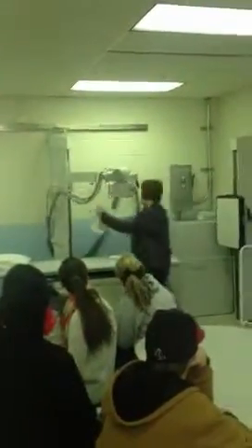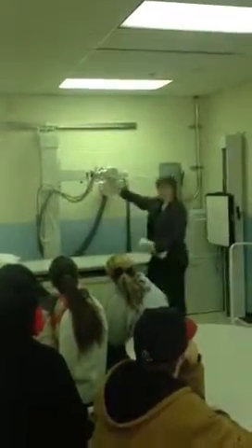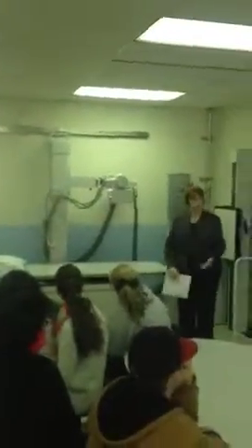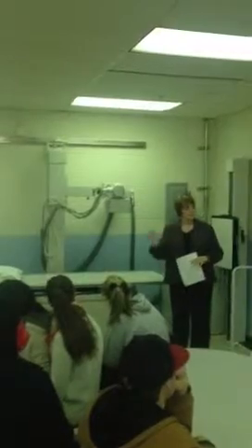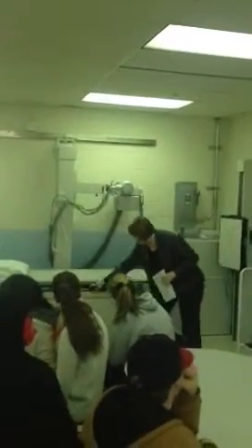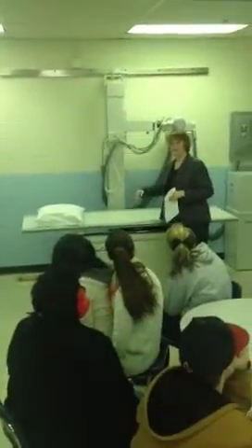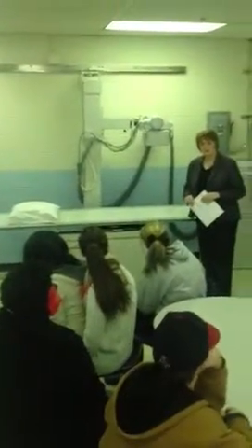Pretend this is a fluoroscopic unit. Use your imagination. X-ray tube's out of the way. You've got your big honker thing here. That imaging receptor assembly is called a primary barrier for fluoroscopy, because your fluoro tube is where? Under the table. So pretending it's a fluoroscopic unit, what's that thingy going along here that we would move our Bucky tray? Bucky slot cover. And what's that little thing that hangs down from our image receptor assembly? Protective curtain. What is the lead equivalency of both of those? 0.25. What about lead gloves? 0.25. What about a lead apron? 0.5. Awesome.